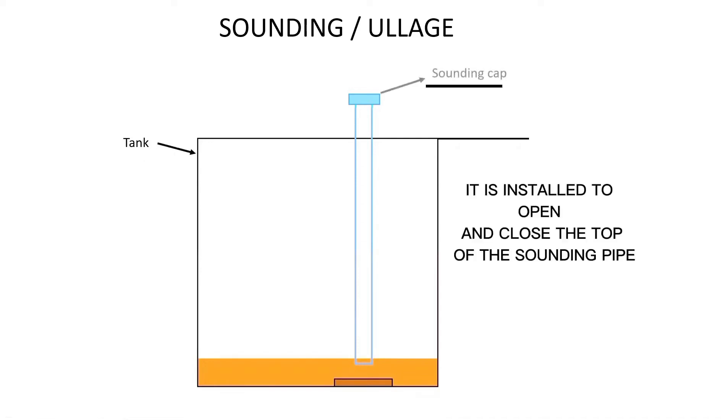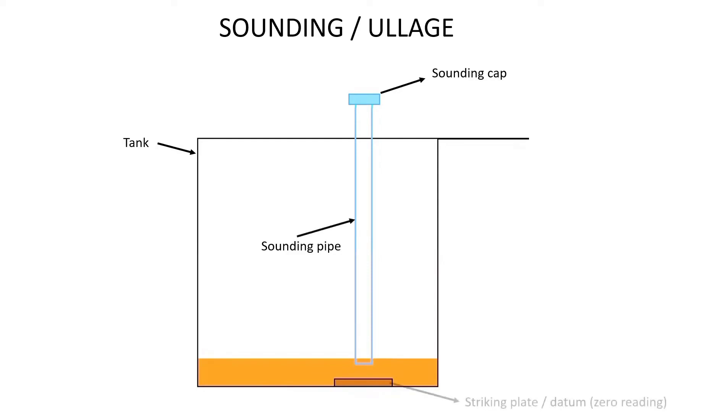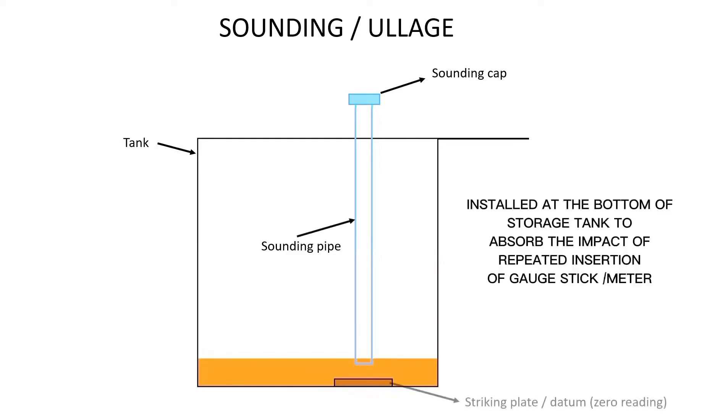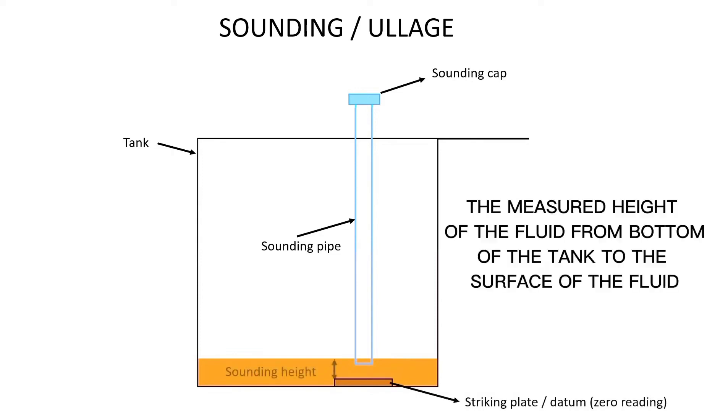Sounding Cap: It is installed to open and close the top of the sounding pipe. Sounding pipe is installed to measure the depth of the fluid filled in the tank. Striking plate, installed at the bottom of storage tank to absorb the impact of repeated insertion of gauge stick and meter. Sounding height, the measured height of the fluid from bottom of the tank to the surface of the fluid.